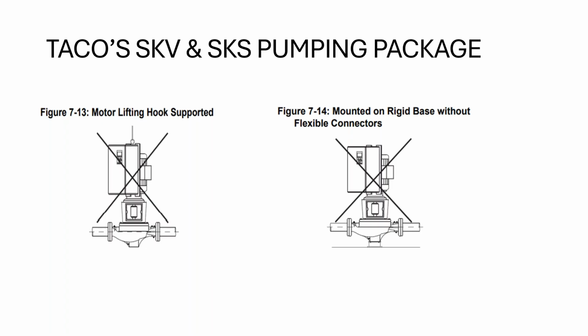But you can see that in some of these pictures here as well. Do not use a lifting hook to lift that drive or motor, please. Motor lifting hook supported. Don't do that. And then mount it on rigid base without flexible connectors. You can't do that either. You'd have to have flexible connectors here to allow that to move. So some of the things you want to talk about or take into account in that regard.